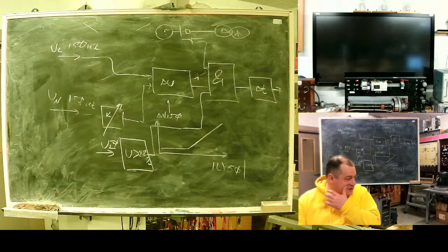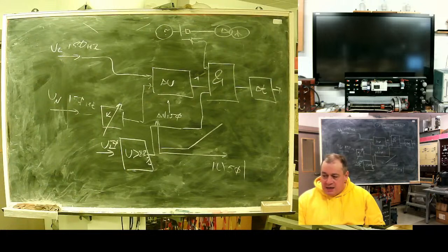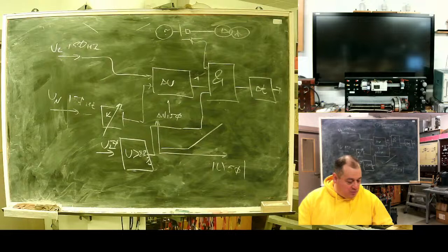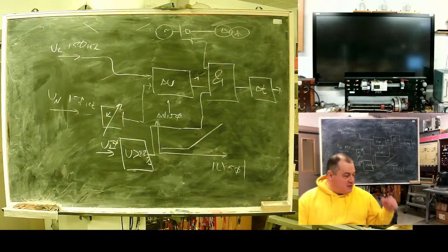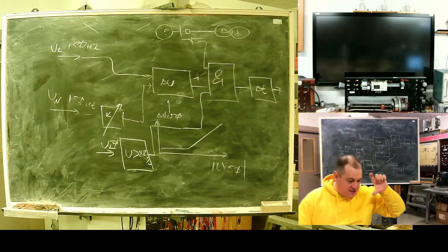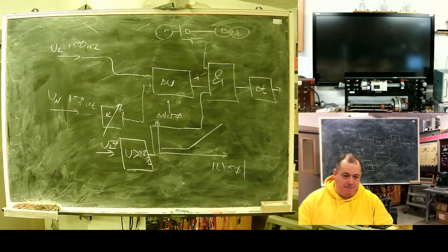Disconnection of these capacitors causes the relay to misoperate. A good idea is to control third harmonic current. Take a current from current sensors and check it for minimum. But this transformer should be before the capacitor. This will check the current of these balancing capacitors.